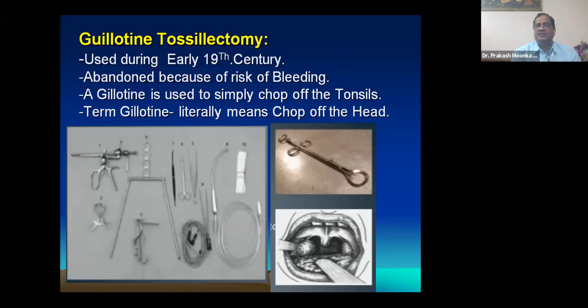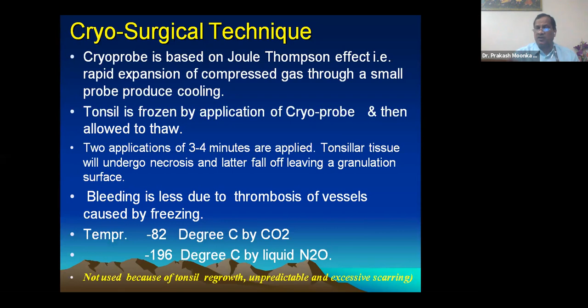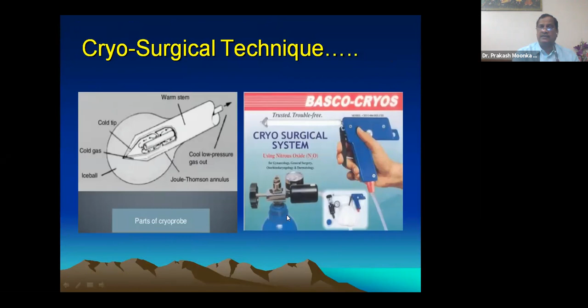Cryosurgery: the cryoprobe is based on the Joule-Thomson effect, that is, rapid expansion of compressed gas through a small probe produces cooling. The tonsil is frozen by application of the cryoprobe and then allowed to thaw. Two applications of 3 to 4 minutes are applied. Tonsillar tissue will undergo necrosis and later fall off, leaving a granulation surface. Bleeding is less due to thrombosis of the vessels caused by freezing. Temperature is -82 degrees by CO2 and -196 degrees by liquid nitrogen. This was postulated to be the best method for children with bleeding diathesis, but it was not used because of tonsillar regrowth, unpredictable and excessive scarring. This is the cryoprobe, you can see, and this used to be the instrument we used in a few cases in the early 90s.